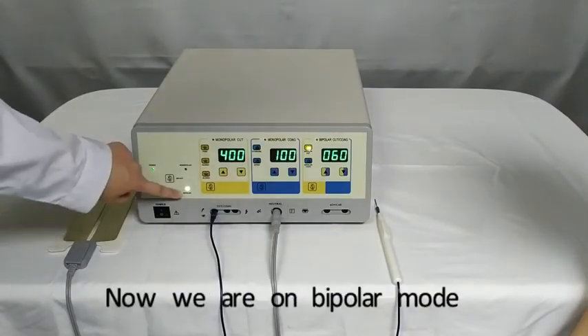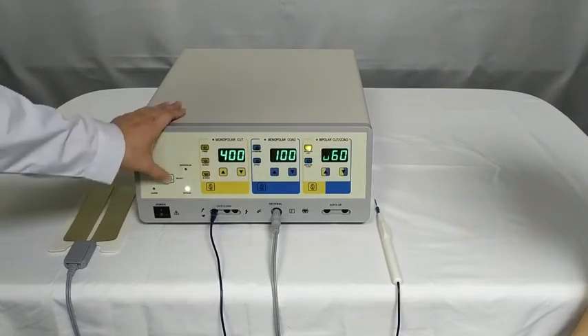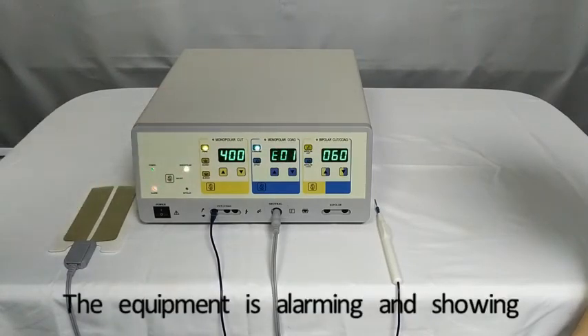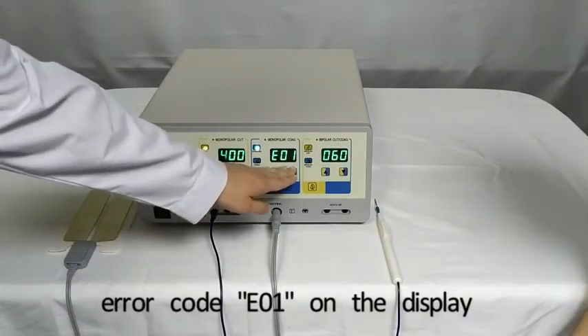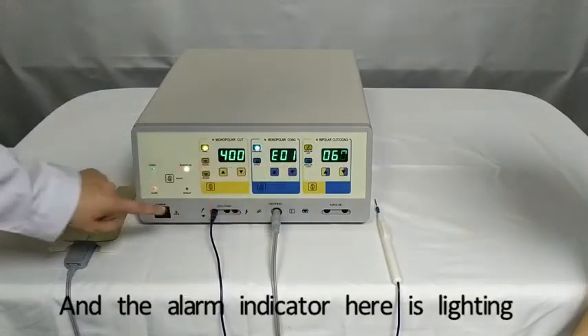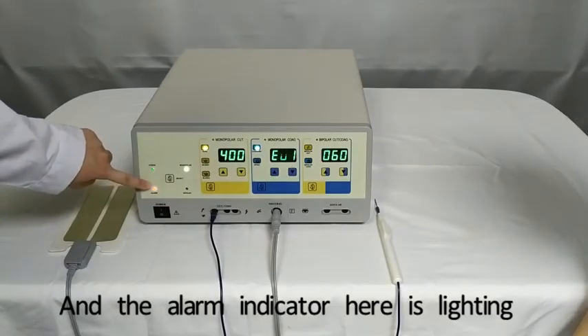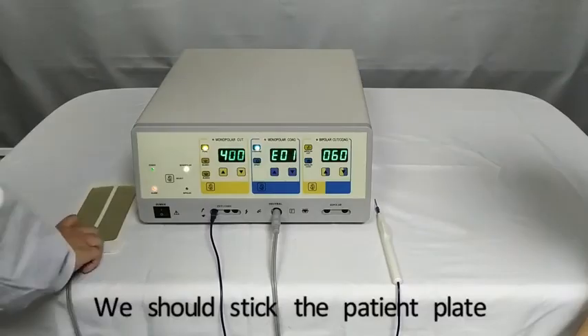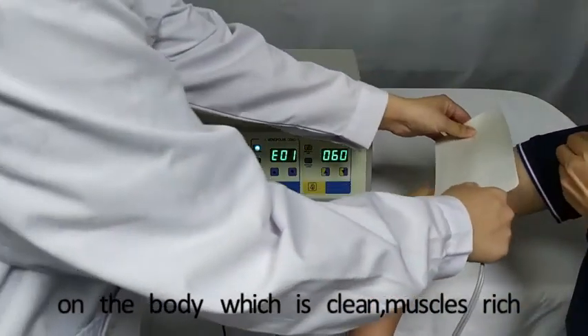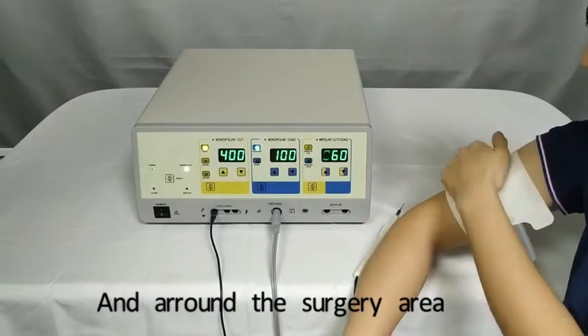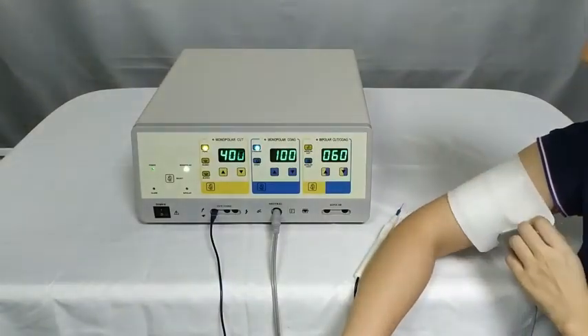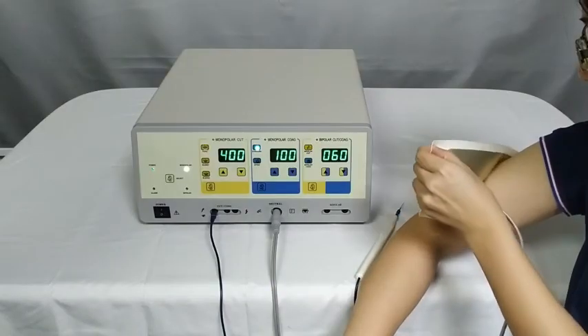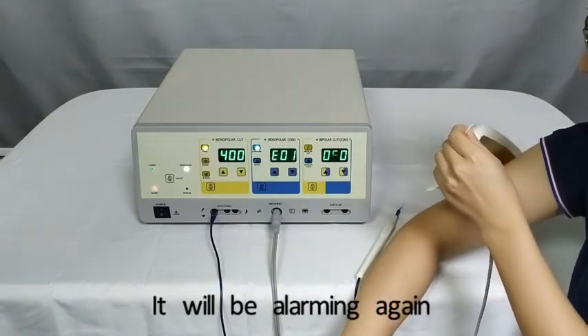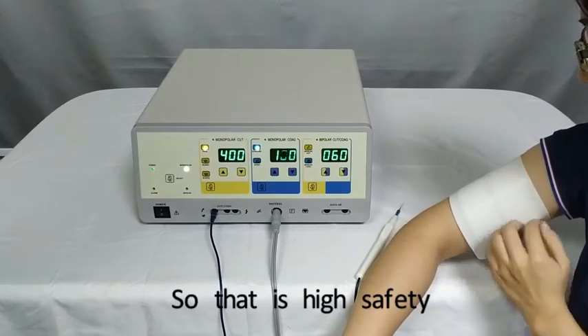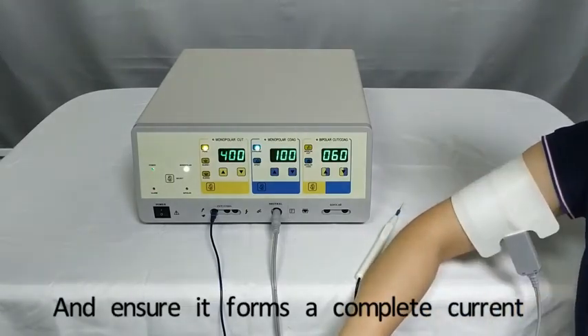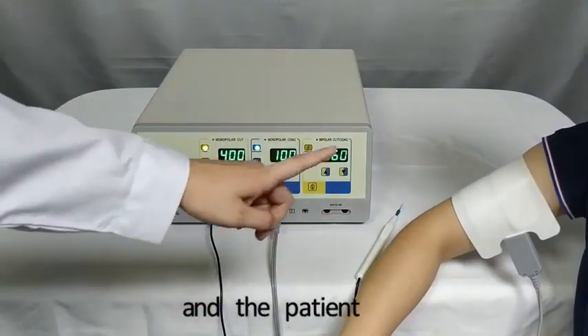Now we are in bipolar mode. Let's change to monopolar. The equipment is alarming and showing error code E01 on the display, and the alarm indicator here is lighting. So what will be next? We should stick the patient plate on the body, on a site which is clean, muscle-rich, and around the surgery area. If we lose the patient plate, it will alarm again. So that is high safety and ensures it forms a complete current circuit between the equipment and the patient.